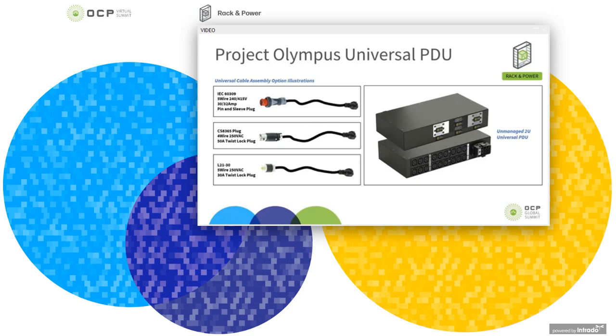Now, to achieve this, we use two pole overcurrent protection shown on the image on the right. And this makes it so we can protect circuits in Y or delta configurations. This PDU was launched with 18 C13 outlets in a 2U configuration.